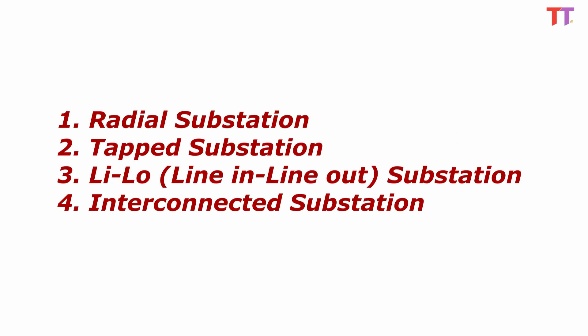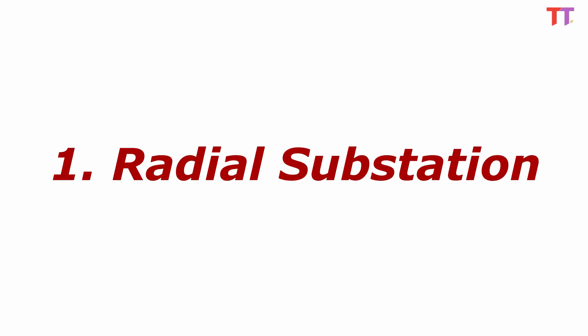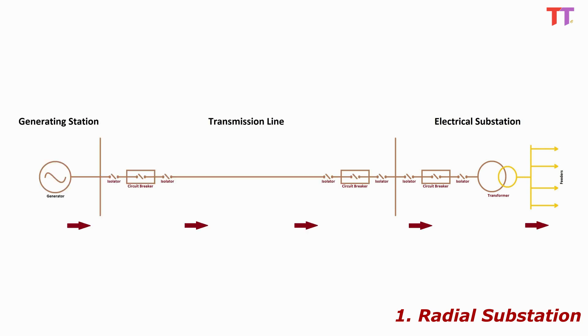So let's start with different schemes or layouts of substation interconnection. 1. Radial substation. In this type of layout, an electrical substation has a single transmission line as a power source and loads are connected at respective feeders. Since this type of layout needs only one transmission line as a power source, it becomes an economical layout type.